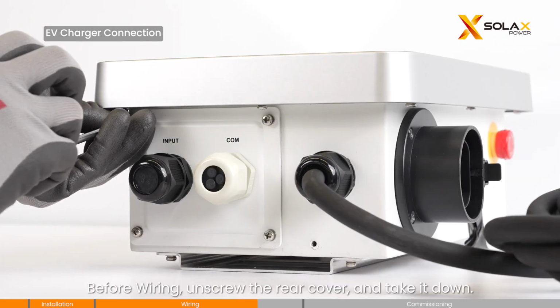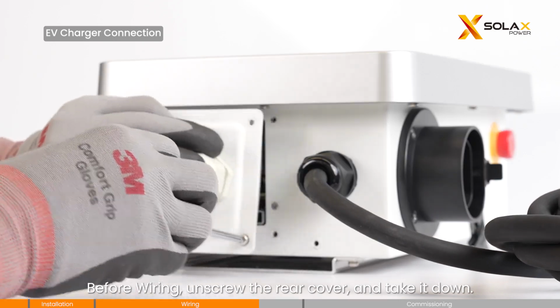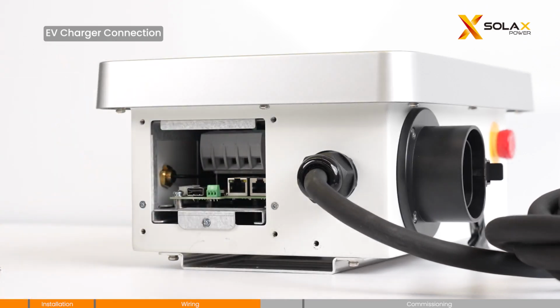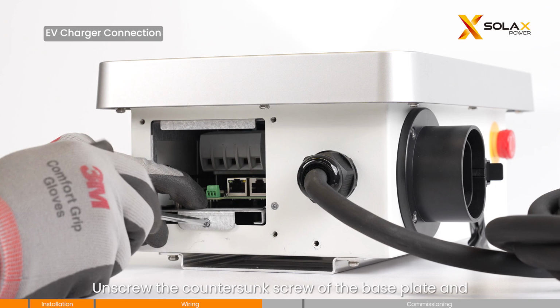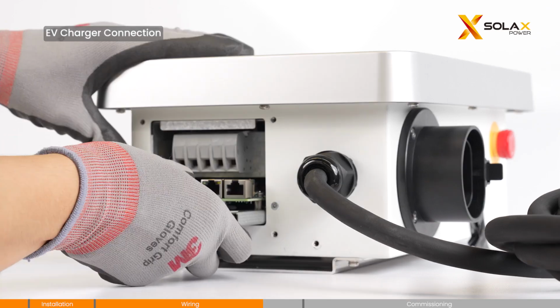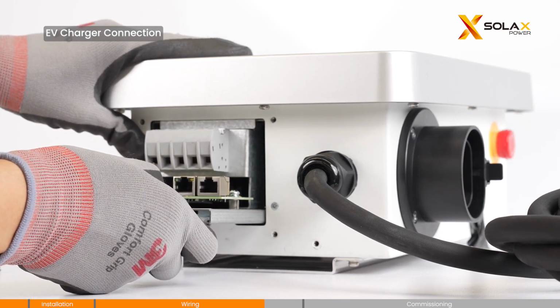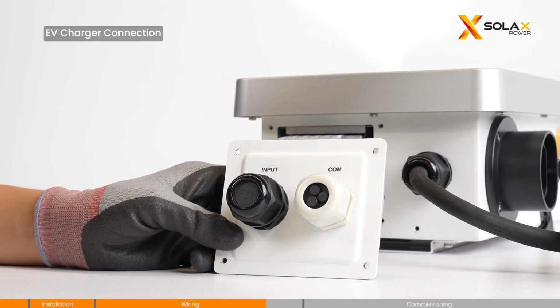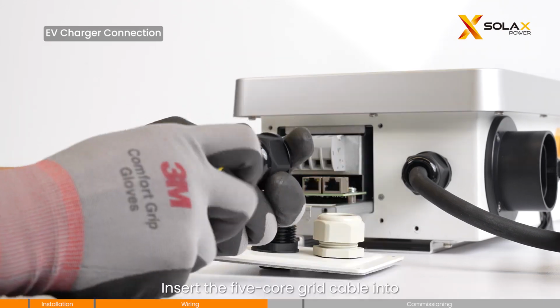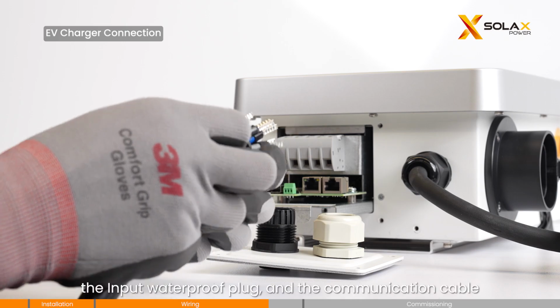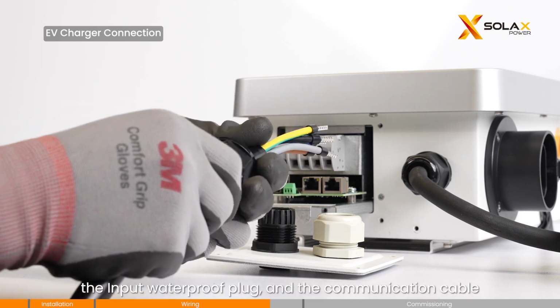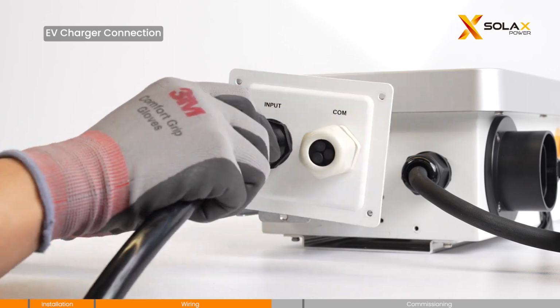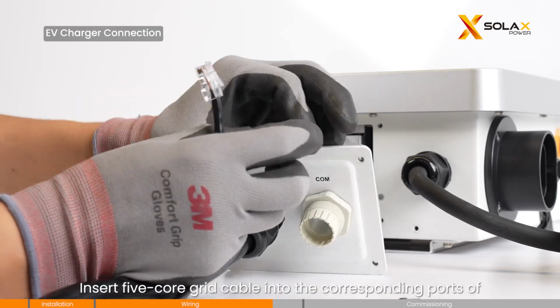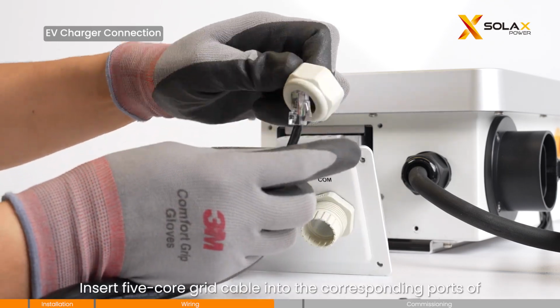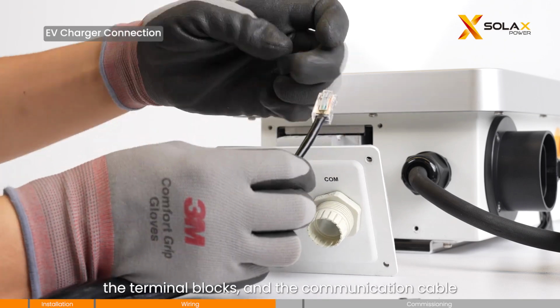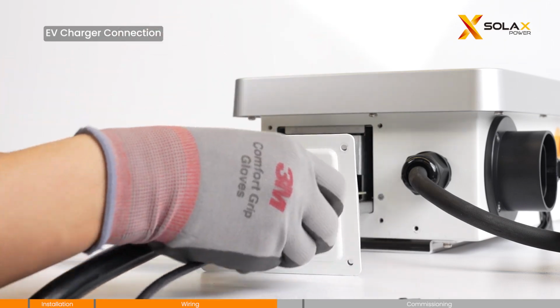Before wiring, unscrew the rear cover and take it down. Unscrew the countersunk screw of the base plate and pull the base plate out. Insert the 5-core grid cable into the input waterproof plug and the corresponding ports of the terminal blocks. Insert the 5-core grid cable into the input waterproof plug, and the communication cable into the COM waterproof plug.